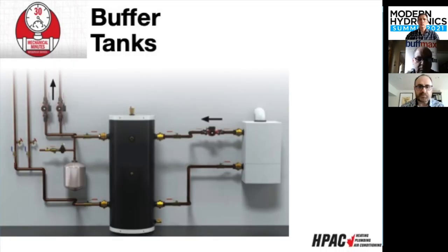It's a good thing. And fundamentally, how it works is it creates what is called a buffer, or they're sometimes called mass tanks. They are mass, which is weight or water, a lot more mass, which gives the boiler something to heat up in essence. And one of the dirty little secrets of our industry, that I call it, is short cycling. We like to design very efficient systems. We have modulating boilers. We want to make things that work very well and efficiently, but there's limitations to that. And any combustion appliance, whether it be a boiler or your car, anything that burns any kind of carbon fuel, they all work better and more efficiently when they work in their full state. When they're running hot, basically, in their full state efficiency, we call it.